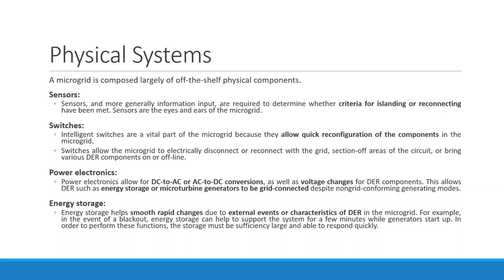Therefore the capacity of the storage should be sufficiently large, and it should respond quickly. Batteries, for example, can respond quickly. You are using a UPS at home, and within a minute, or fractions of a second, you are in a position to get backup power if a battery is there. If a generator is there, even though it is automatic, it takes at least 1 minute to supply you, because these things take time.